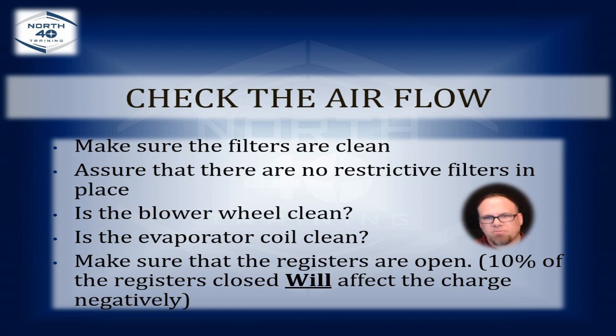Now, if you've got a multi-speed blower, the multi-speed blower doesn't know that you've closed all those registers. It's still trying to push down those runs. And just because you close off those registers doesn't mean the airflow is automatically going to go to a different run, say to the second floor or to the weird bedroom above the closet or to the new addition that you've put in that never had good airflow. It just doesn't work that way.